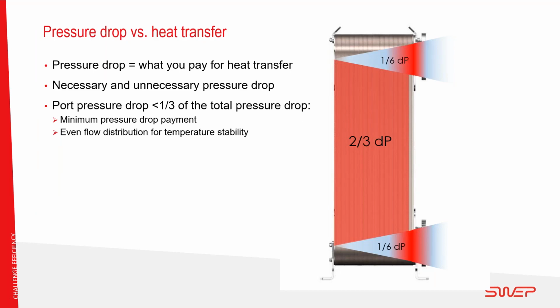So now considering pressure drop against heat transfer. As previously mentioned, in order for the heat transfer to occur, the payment is pressure drop. Therefore, what we want is for the pressure drop to occur within the plate channel itself where the heat transfer happens, and to minimize the pressure drop elsewhere. The ports must be big enough as to not create a large restriction to the flow. As a rule of thumb, we say that the pressure drop in the ports must not exceed 1/3 of the overall pressure drop. This also allows an even flow distribution, which keeps the temperatures stable.